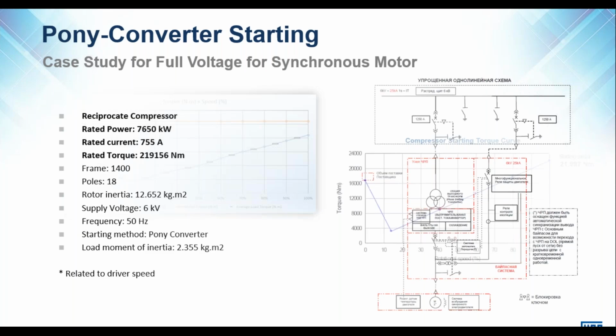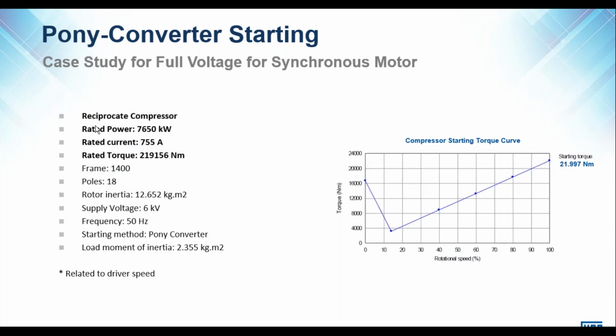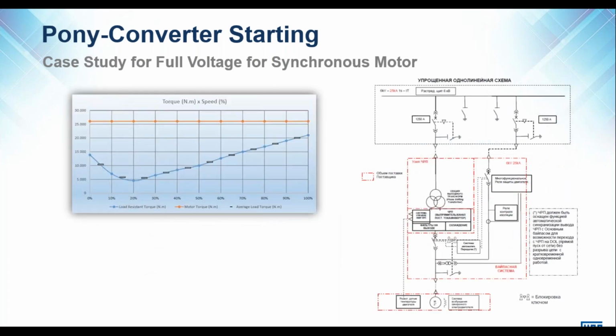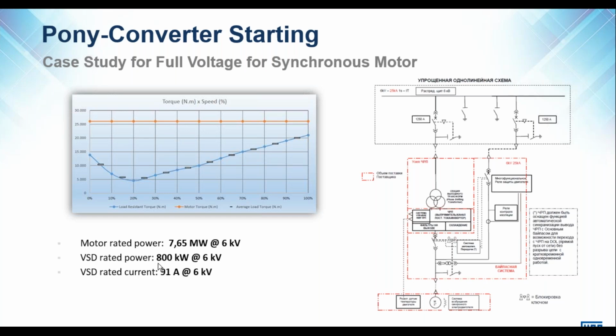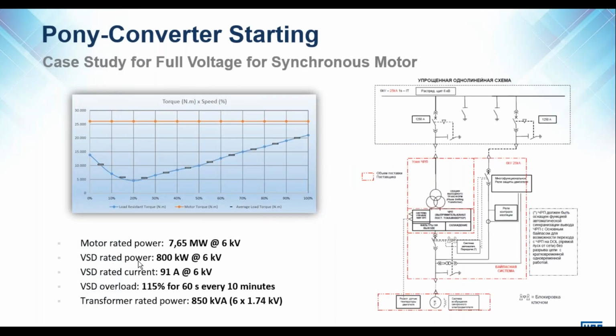Okay, here's a specific example of what I'm talking about. In this case, we had a reciprocating compressor. The motor rated power was 7.6 megawatts, and the supply voltage was 6 kV. Because the end of load curve was dramatically reduced compared to after acceleration when the load is applied, we were able to start this load with a VSD rated 800 kilowatts. So we're talking about a 7.6 megawatt machine, but using an 800 kilowatt 6 kV VSD to start that load and ramp it up to speed.